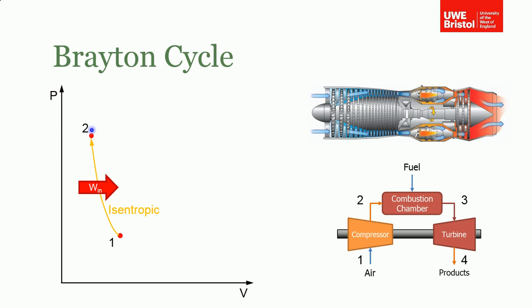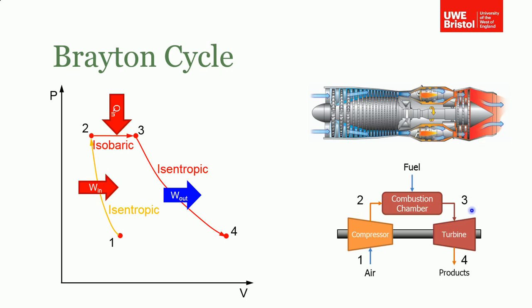From two to three, we add heat by burning the fuel. This is an isobaric process because there can't be any pressure build-up — the cans are open and exhaust products can come out, so it's a constant-pressure, isobaric heat addition. The exhaust gases then flow over the turbine from three to four, and work is extracted isentropically as the pressure drops back down to atmospheric.